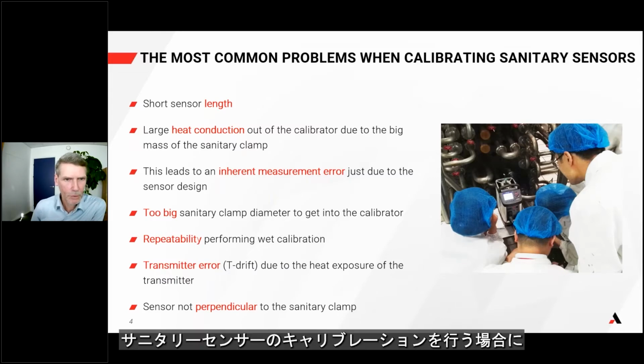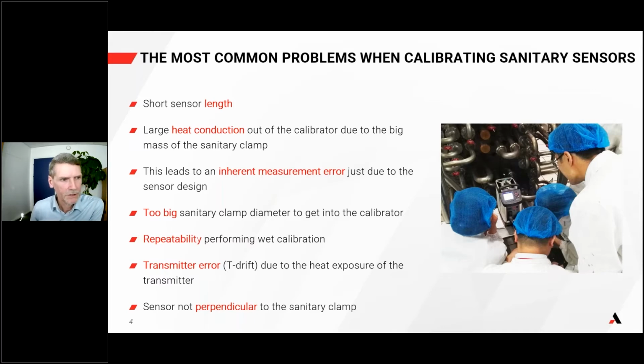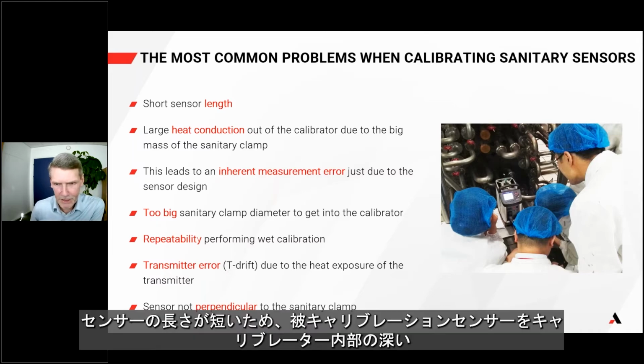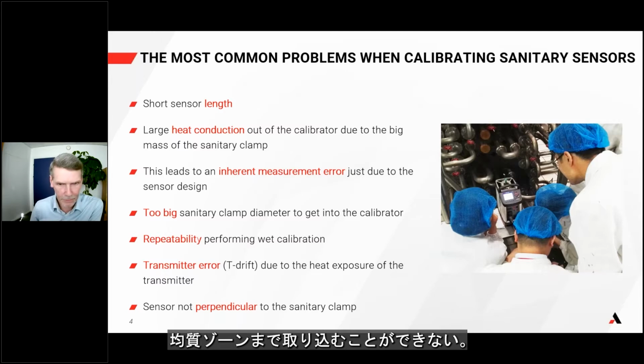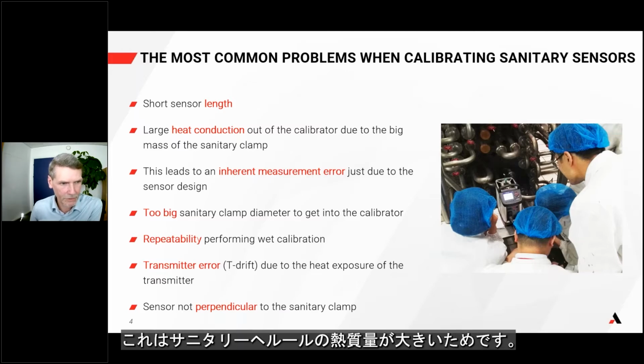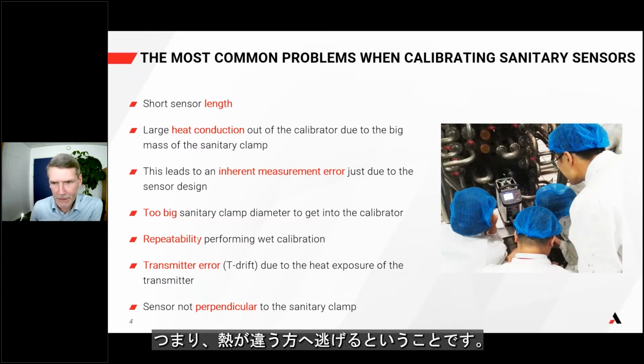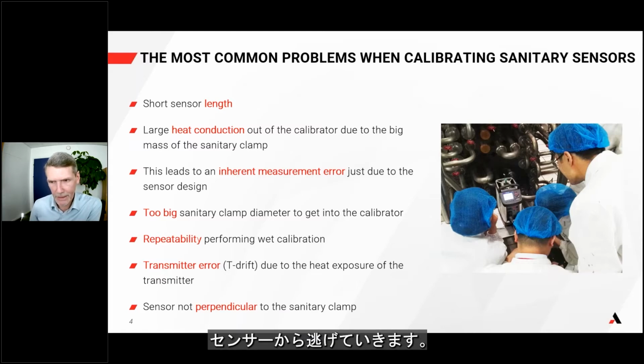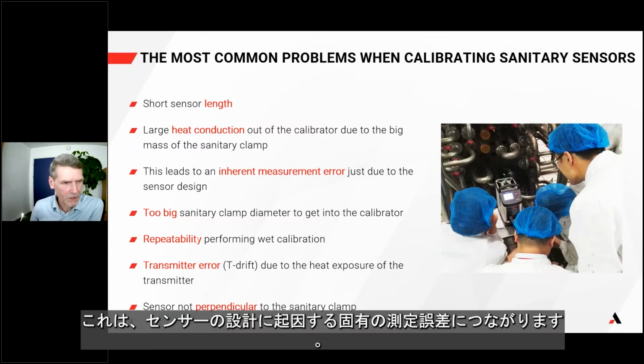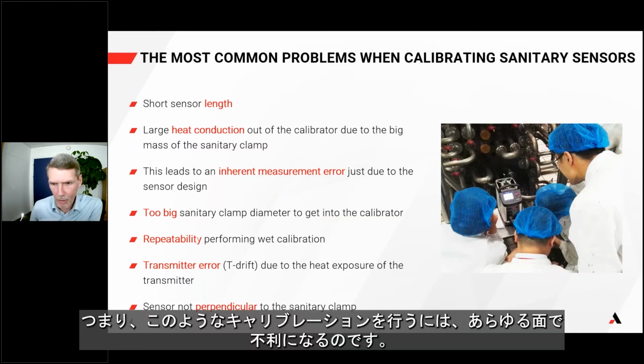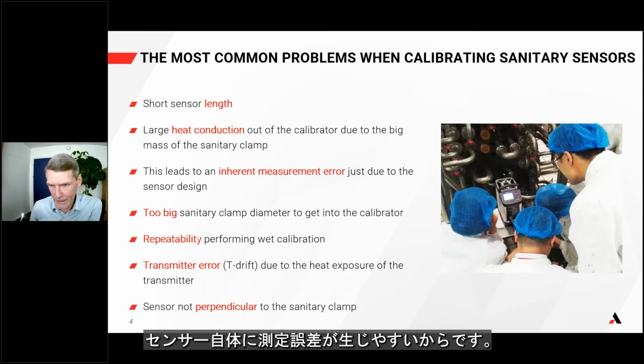The most common problems when calibrating sanitary sensors. Short sensor length. Since these sensors are short, we cannot get the sensor under test down into the homogeneous zone of the calibrator. Large heat conduction out of the calibrator due to the big thermal mass of the sanitary clamp, meaning that the heat is going the wrong way. In other words, the heat is going out of the sensor instead of going into the sensor. This leads to an inherent measurement error just due to the sensor design, meaning that we have all odds against us performing these calibrations, since the sensor itself tends to create a measurement error.